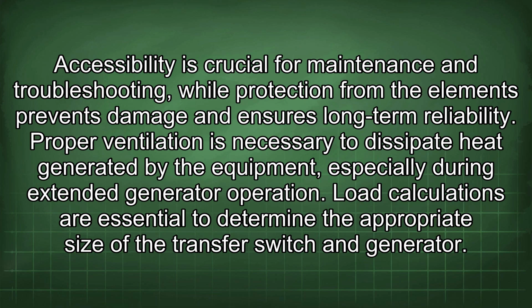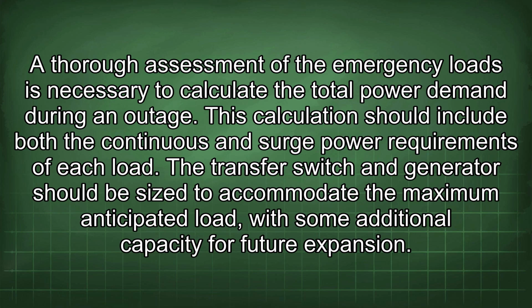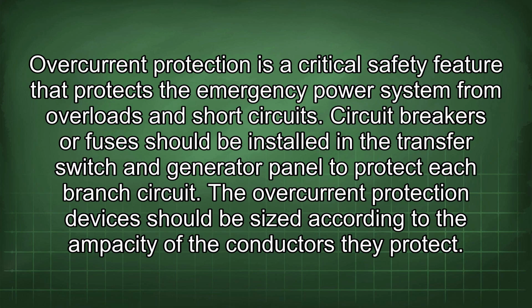Load calculations are essential to determine the appropriate size of the transfer switch and generator. A thorough assessment of the emergency loads is necessary to calculate the total power demand during an outage. This calculation should include both the continuous and surge power requirements of each load. The transfer switch and generator should be sized to accommodate the maximum anticipated load with some additional capacity for future expansion.